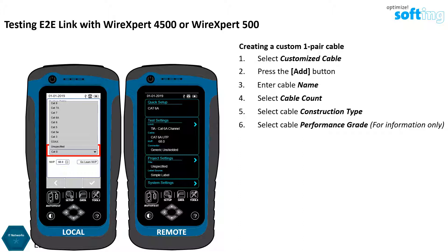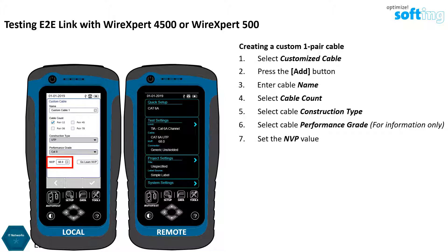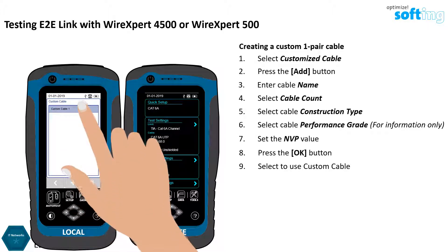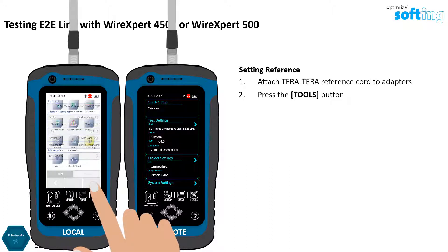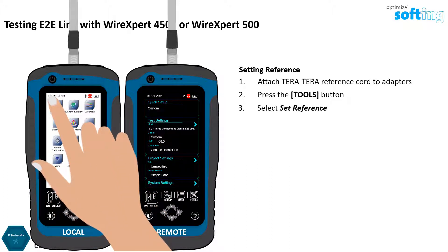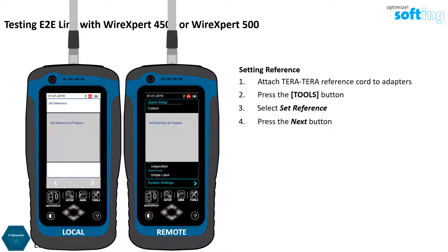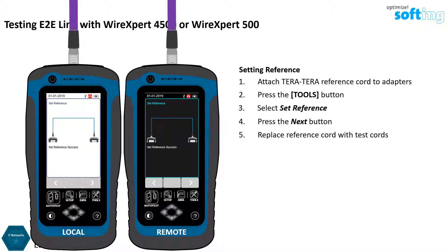Hence, it is important to select the correct option to be documented for future references. Enter the correct NVP value — this is the same option as in the test settings — and press OK to proceed. Select to use the custom cable. Perform a set reference using the TERA-TERA reference cord provided in the kit. Press the Tools button on the local unit and select Set Reference, then press Next to proceed.